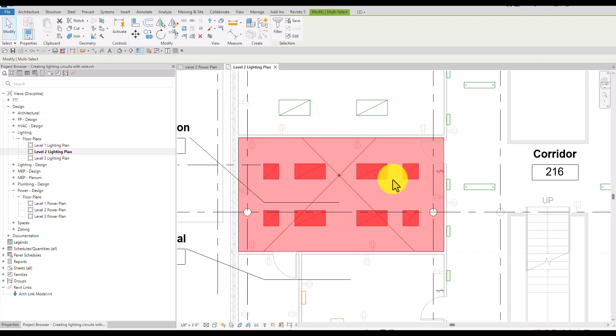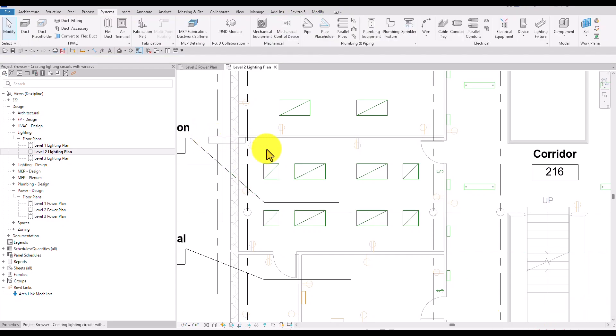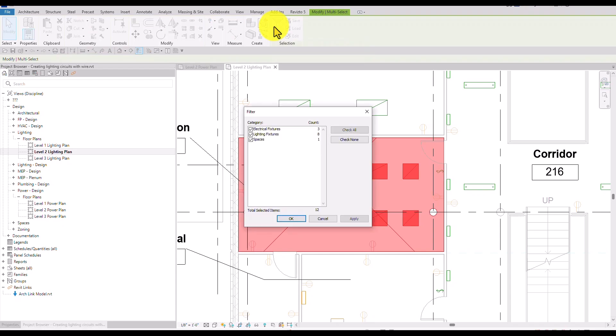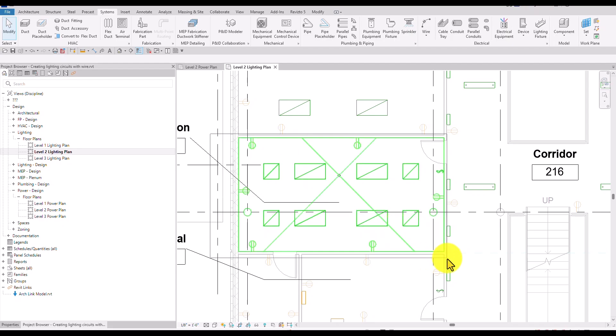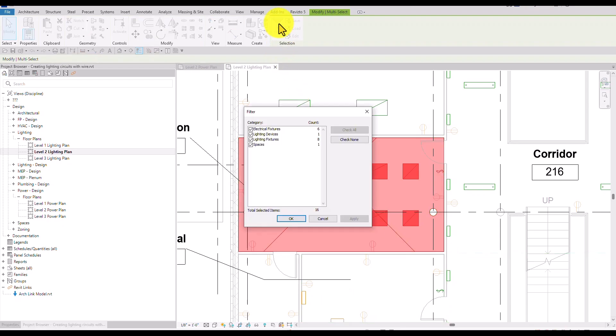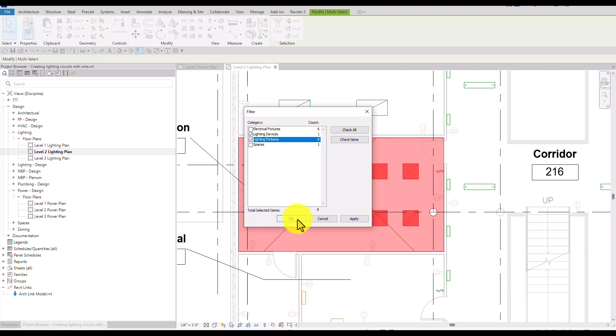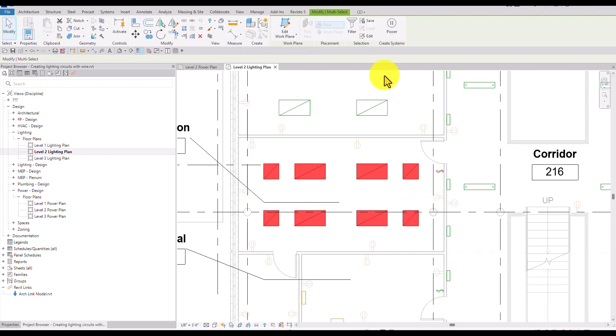If you're having trouble selecting all the elements, make sure you disable Link Underlay, Pin Elements, and Select Elements by Face. With those disabled, I can make a window selection to select all elements within that space. Then I'll use Filter, check None, and select only Lighting Devices and Lighting Fixtures, then click OK.